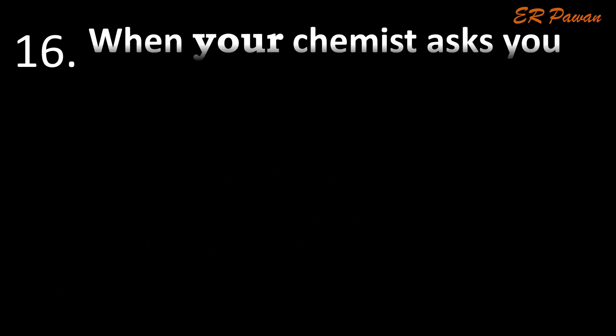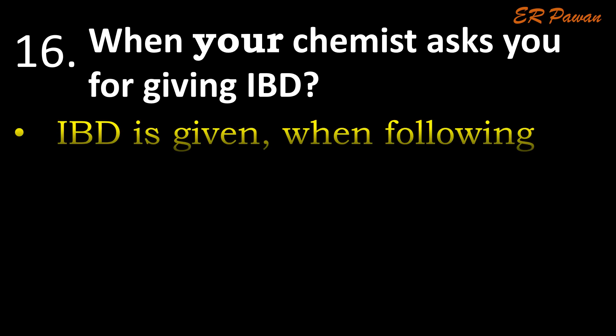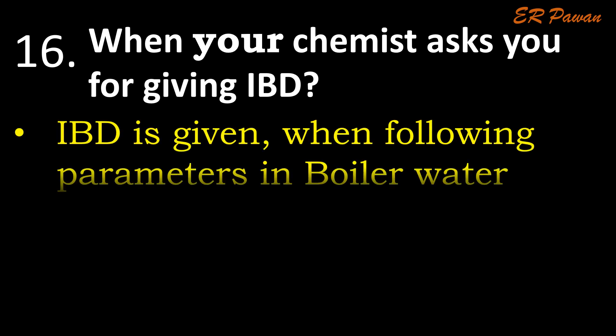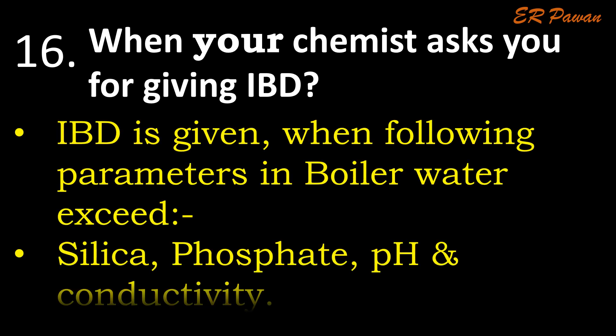Question 16: When does your chemist ask you for giving IBD? IBD is given when the following parameters in boiler water exceed: silica, phosphate, pH, and conductivity.